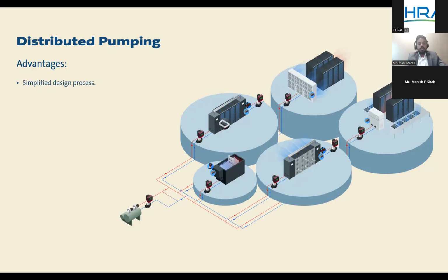What is challenging is identifying the exact change in demand. So in today's design process, how are we doing it? Are we addressing the flow requirement based on temperature feedback? No. It's an indirect way of identifying the flow, which is a pressure based system. We modulate the system based on the temperature requirement on the load side, and that is translated to the valve. When the valve moves, it creates a differential pressure. We have to identify which is the critical load, place the DP sensor or differential pressure sensor, and take that feedback to the primary pump or secondary pump to distribute the flow. So the design of the system is a little complex. It's not direct, it's an indirect way of doing it.